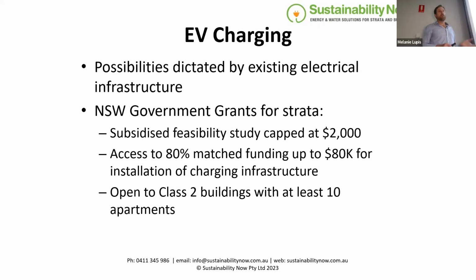It costs several hundred dollars to make an application to Ausgrid to get that checked. The other problem is that a lot of these older buildings don't have a main switch coming into the site, just cables coming straight from the substation into the board. So it's hard to tell what the maximum demand of the site can be before you're causing problems downstream. That's hard on some of these buildings.